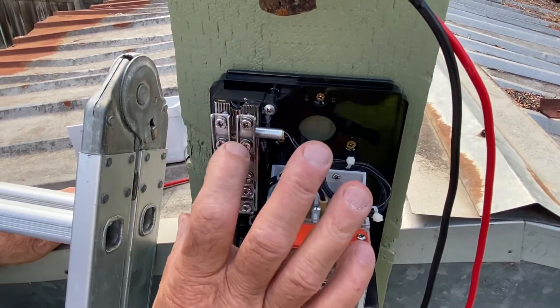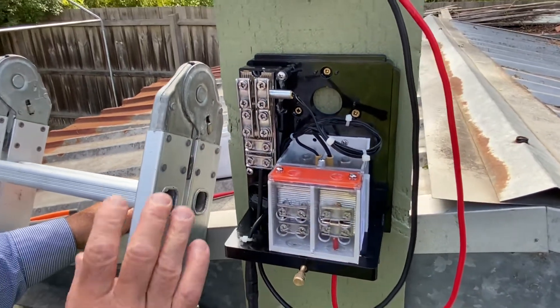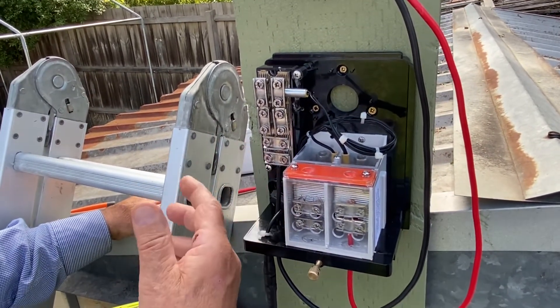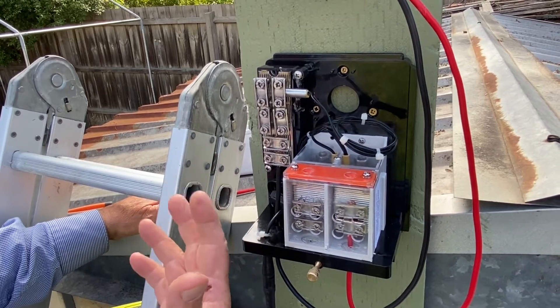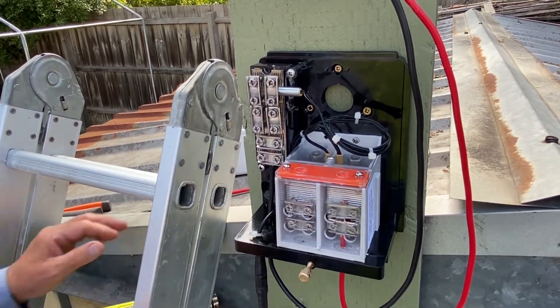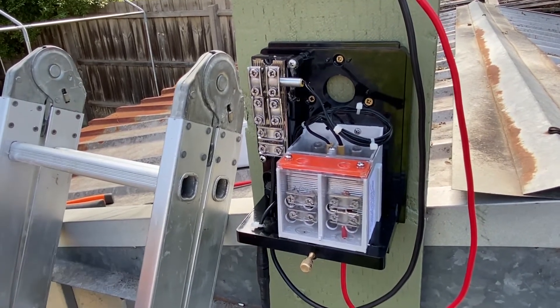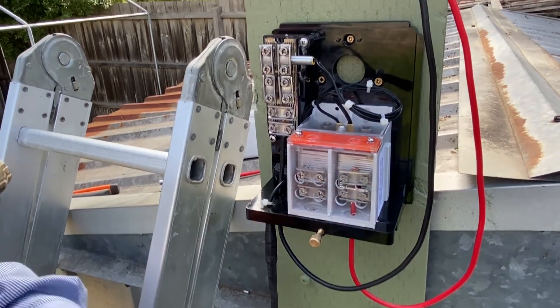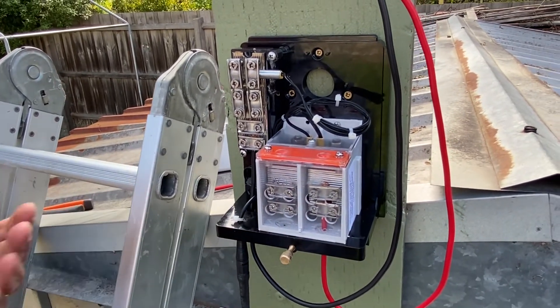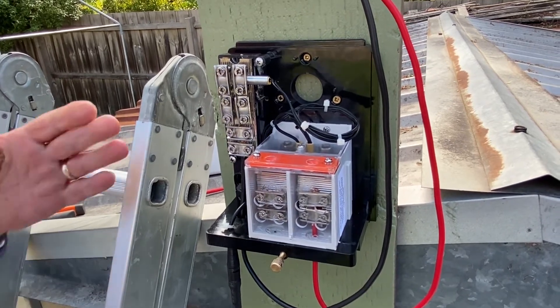I'm going to apply heat as if it was building up inside that block, or inside these blocks. These things usually take a time to get hot, so it's very difficult to get an instantaneous effect of high-resistance joints. But we're going to do that with the aid of a heat gun. I'm going to place the heat gun on, and in this particular case it is latched to an alarm, which could be a smart meter or whatever else. Here we go — it's hot.